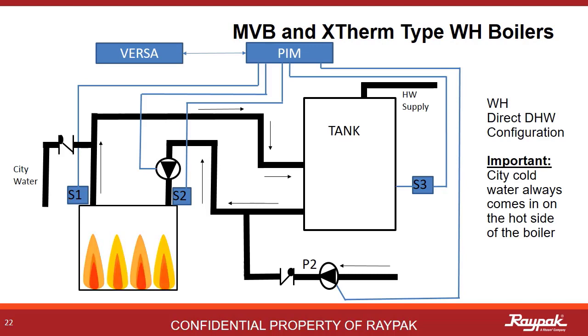Moving on from hydronic and into type WH appliances — as in water heaters. With an MVB or X-Therm purchased to be a water heater, there is only one mode of operation, so the plumbing is more specific. Here is a drawing for a water heater application. Important notes: city cold water always comes in on the outlet side of the boiler to be mixed with the hot water the boiler is producing on the way to the tank. Introducing the city cold water on the inlet side of the boiler will likely lead to going below the required minimum inlet temperature of 120 degrees Fahrenheit, resulting in condensing in the wrong part of the boiler. Here the tank works like a decoupler, and the S3 system sensor is placed in a dry well in the tank.